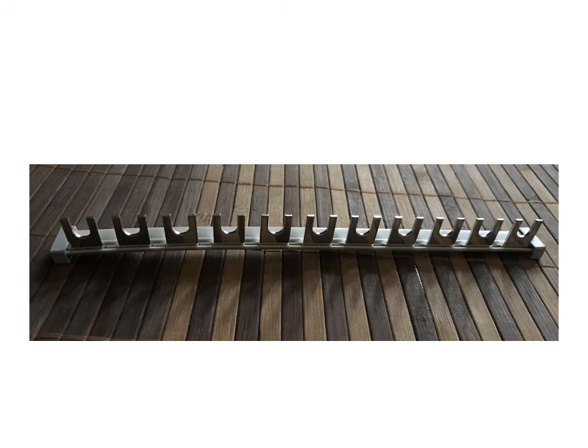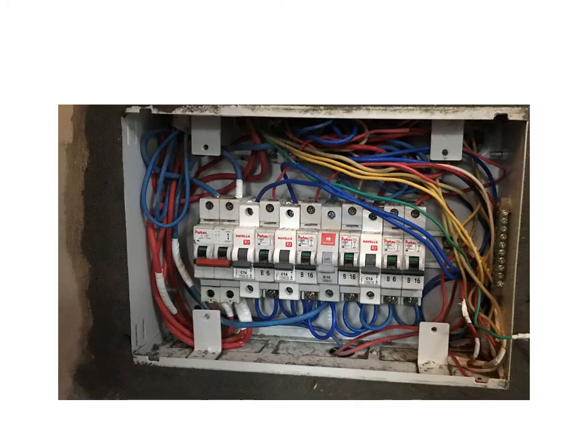So this is the bus bar. So all the MCBs will be connected by this bus bar. So these are MCBs connected. Here we have not used that bus bar because all the MCBs that we have used here are of different sizes. So if we want to use a bus bar for these MCBs, all the MCBs should be of the same company, or you can say of the same size. So it was not possible here. So we have used different MCBs here. So the phase is given by a wire, not through the bus bar.